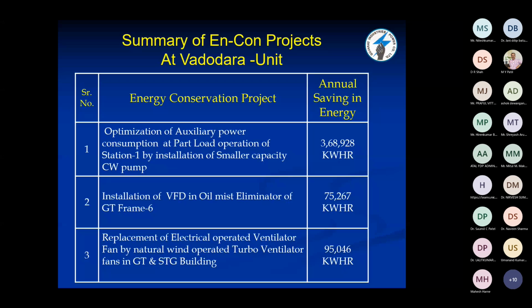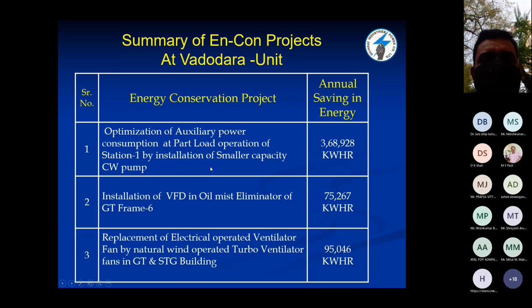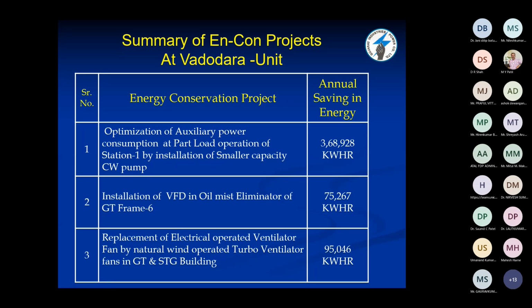So these are the main energy conservation projects that we have carried out at Vadodara unit. Number 1 is optimization of auxiliary power at part load operation of station 1 by installation of smaller capacity cooling water pump. Now, in this steam turbine, the major power consumption is in the condenser. So when the machine is running at part load, the water requirement is very less, but the pumps that are installed for that are running at full load. So in that case, we can optimize the power consumption. I will show you the detail of how we have done that in a coming slide.